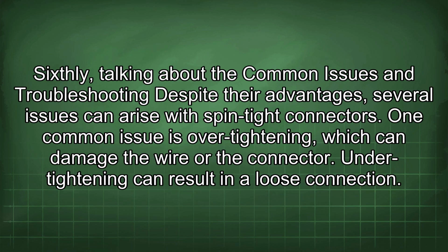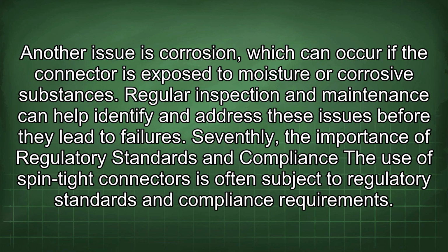Sixthly, talking about the common issues and troubleshooting. Despite their advantages, several issues can arise with spin-tight connectors. One common issue is over-tightening, which can damage the wire or the connector. Under-tightening can result in a loose connection. Another issue is corrosion, which can occur if the connector is exposed to moisture or corrosive substances. Regular inspection and maintenance can help identify and address these issues before they lead to failures.